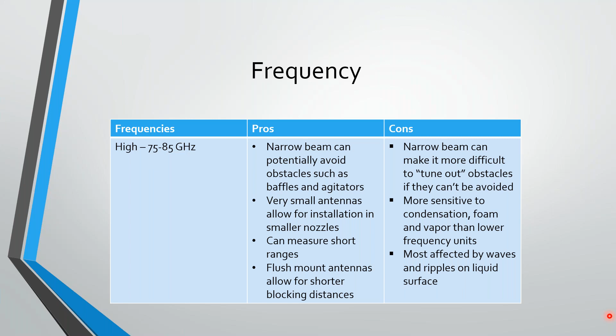So some of the cons. Well, that narrow beam, if you do have obstacles that you can't avoid and you're trying to tune them out, it's going to be more difficult with a higher frequency device. It's also going to be more affected by waves and ripples because, again, it's just a narrower beam and it's not averaging out across the widest surface of that liquid. It's going to be a little more sensitive to foam and vapor and things like that. But still, these units do work very well in a whole slew of applications. Again, there are some small areas where you want to go to the lower frequency device instead of this.